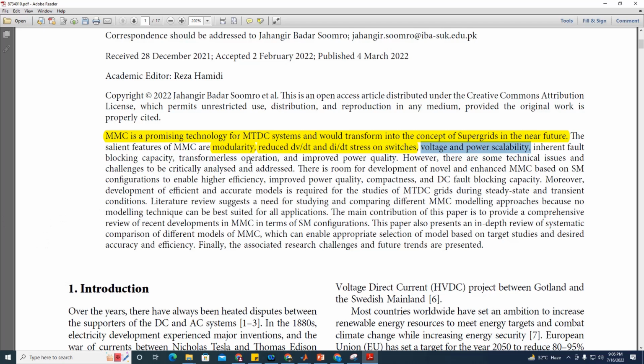Transformerless operation is possible with MMC, which improves power quality. If you increase the number of sub-modules, say n equal to 50, then with conventional nearest level modulation you get 51 levels. If you check the FFT of this 51-level output voltage, the harmonics are expected to be below 5%, so without needing any filter, you get better power quality with MMC.